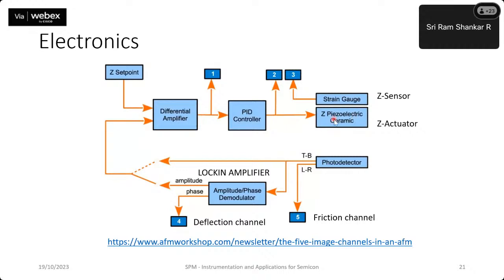The motion of such a piezoelectric stage can be monitored through a Z sensor, which can either be a strain gauge, a capacitive-based strain gauge, or a capacitive-based displacement detector, and so on. With this, we had a brief look into the integral components of any AFM system.